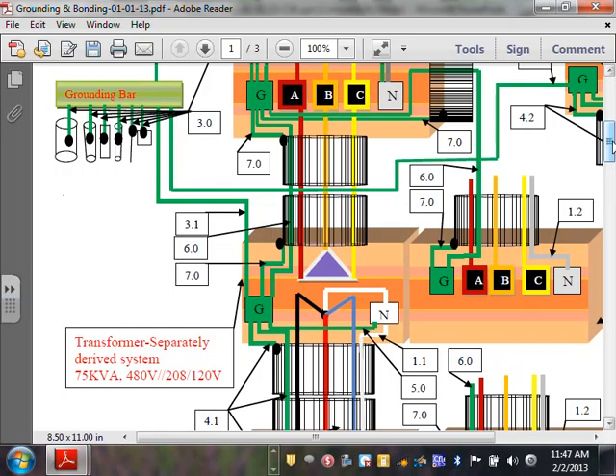Good point, guys. Any comments, any questions? So we went 3.1, you don't have to go all the way to the bar. If you're building steel, you tie to the steel, you're done. That's the only time you can. If you would drive a ground rod right here, you have to tie the ground rod to the other ground electrode system in your building that's not already done.